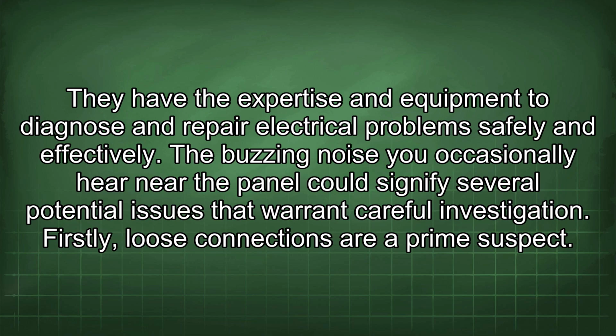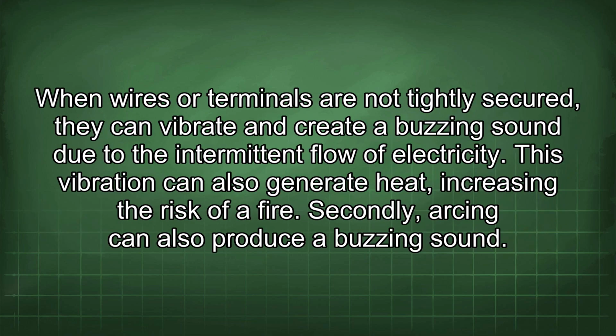The buzzing noise you occasionally hear near the panel could signify several potential issues that warrant careful investigation. Firstly, loose connections are a prime suspect. When wires or terminals are not tightly secured, they can vibrate and create a buzzing sound due to the intermittent flow of electricity. This vibration can also generate heat, increasing the risk of a fire.